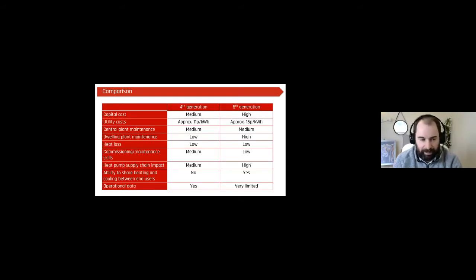So, a quick comparison. This would be within a communal heating system, where you're looking particularly at heat. The capital costs would tend to be higher for a fifth generation system. Well, it would be higher if it was heat only. If you have a very good balance of heating and cooling, then they're closer in cost because of the ability to share heating and cooling, and you only need one plant instead of doubling up with heating and cooling plant.